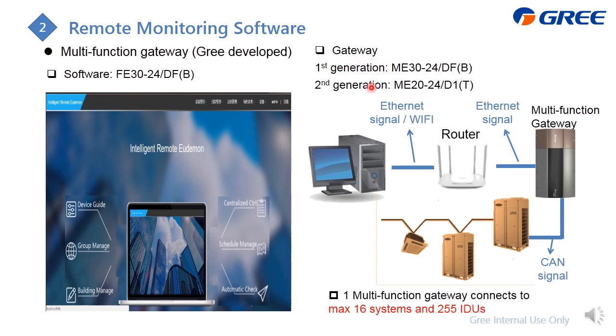And currently there are two generations. And the wiring is also very easy, just from this outdoor unit, the G1, G2, from this CAN signal to the gateway. And from the gateway, we use an Ethernet cable to a router, then to this PC. Then this PC can communicate, which is to check or to send commands to control the GMV system.